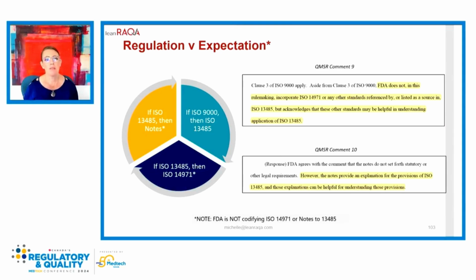Because now we have another set of regulation versus expectation. In the comments to the QMSR that was just released, the FDA specifically says, while we're not codifying 14971 or the notes to ISO 13485, if you want to know what we mean when we say the word risk, or when we're talking about a particular clause, you need to know and understand both ISO 14971 and the notes. So even though they're not codified, they communicate the FDA's expectation in these areas. Next slide, please.